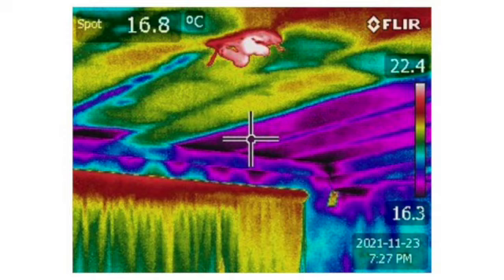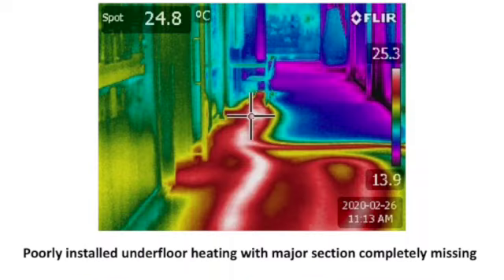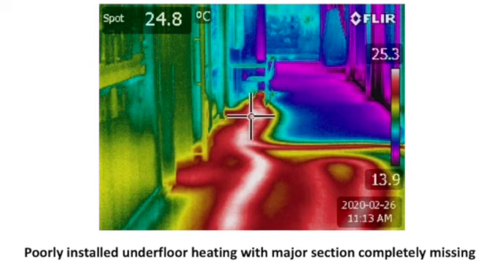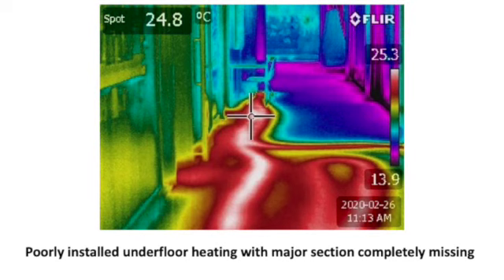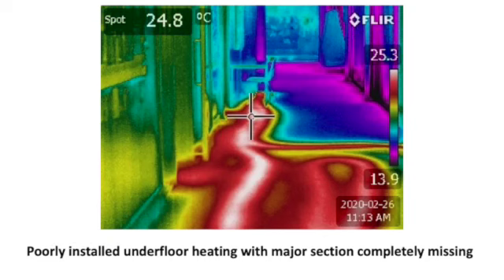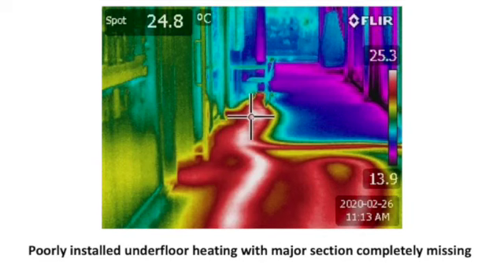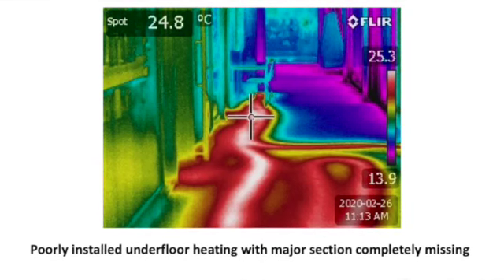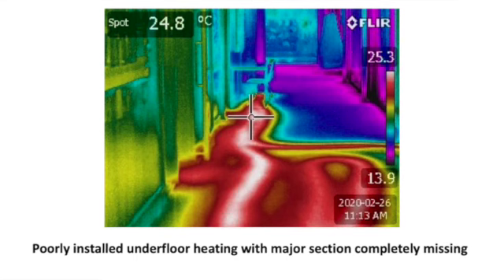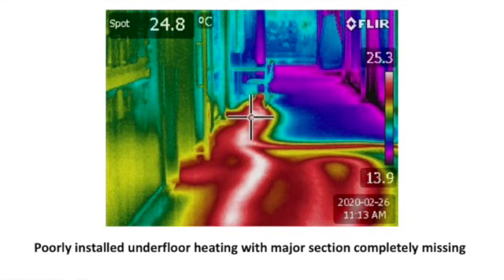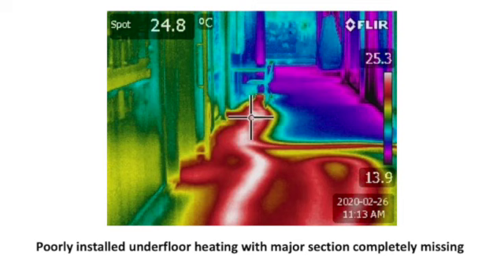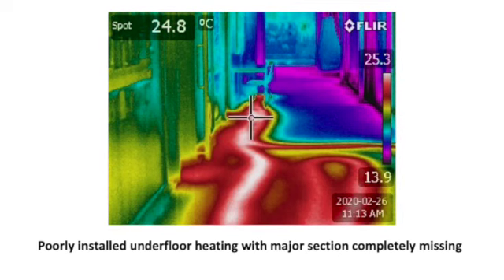Just as missing insulation is not visible to the eye once the builders have finished their work, so unfortunately are many defects under the floor, like underfloor heating, such as this installation in this thermal image where a whole section is completely missing, which was making this area of the building so cold it was unusable.